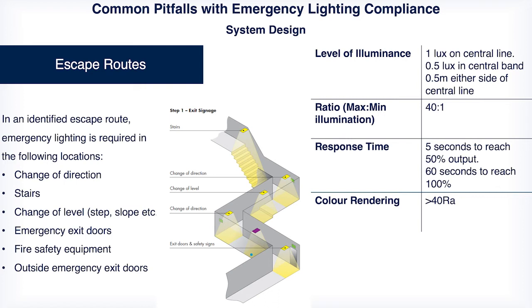The response time for luminaire compliance is very rarely not met. 5 seconds to reach 50% output. This was traditionally in there for all the fluorescent products that took time to get up to full output. LED as a light source operates on 12 volt anyway. Most LED sources are operating at 12 volts, so getting to full output with an LED light source is not really an issue. Color rendering index must be 40 or above. Once again, not a difficult level to achieve, with the vast majority of LED products these days being at 80 or above for their Ra.